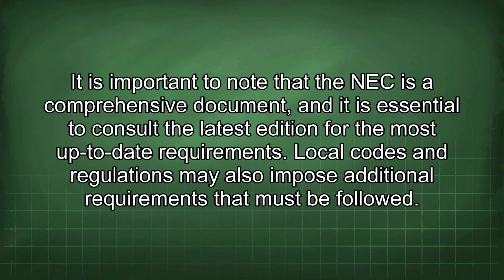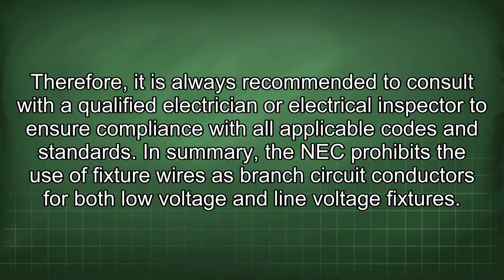Local codes and regulations may also impose additional requirements that must be followed. Therefore, it is always recommended to consult with a qualified electrician or electrical inspector to ensure compliance with all applicable codes and standards. In summary, the NEC prohibits the use of fixture wires as branch circuit conductors for both low voltage and line voltage fixtures.